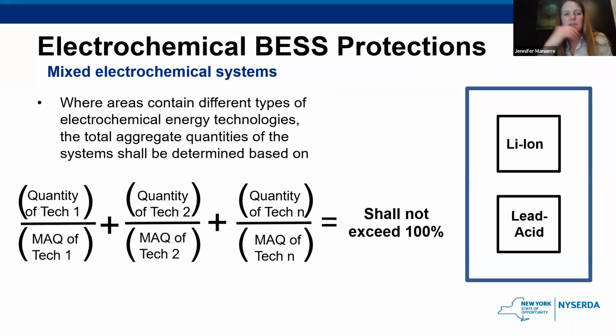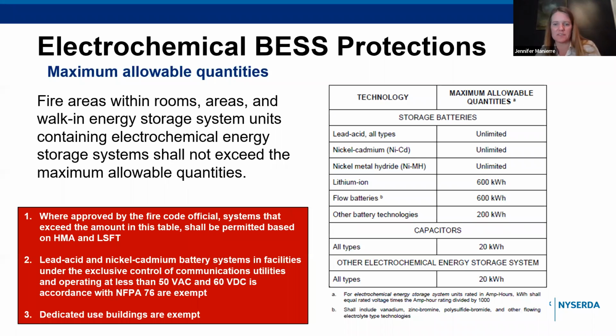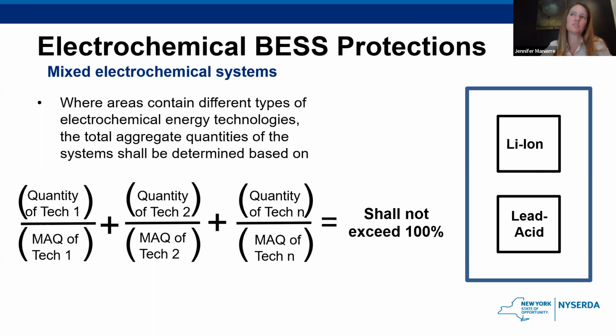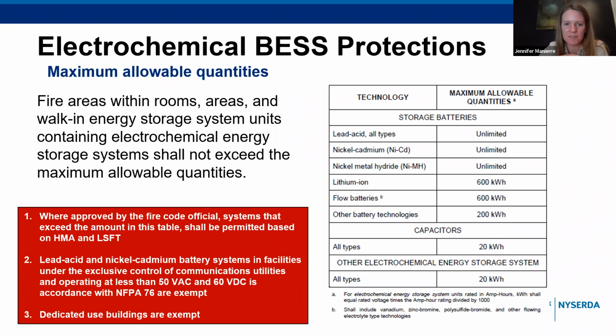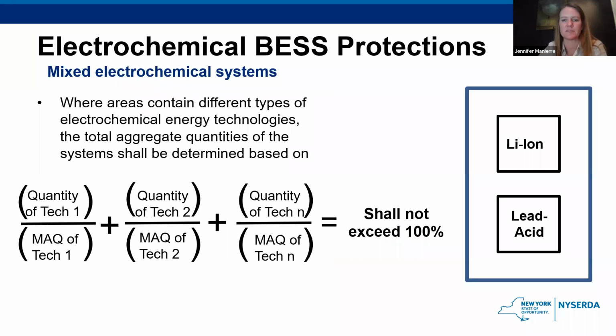Probably not too common, but in some instances, you might see different technology types in the same room. And so to determine the maximum allowable quantity, if you have more than one, you can't just say, oh, well, the max for lithium ion is 600 kilowatt hours, and the max for, let's say, flow batteries is 600 kilowatt hours, so that means we can have 1,200 kilowatt hours worth of batteries in a room. No, you do sort of a weighted average, if you will. And that's just what this equation here is showing. So even if you were to combine those two types, like lithium ion and flow batteries, it's still a max of 600 kilowatt hours. You don't get to double it up just because you're mixing battery types. That's all that it's showing.